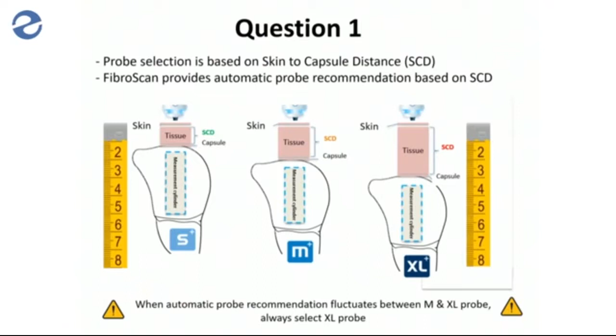We could be tempted, because the XL probe helps applicability of the FibroScan, to scan everybody with XL. We also hear very often that if you compare M and XL probe on the same patient, there are lower values with the XL probe compared to the M probe. What we should stress is that because each probe is dedicated to one type of patient, we shouldn't compare two probes on the same patient, because we are comparing different measurement depths and different ultrasound frequencies. What often happens is, if you scan an overweight patient with the M probe, you get unreliable results because of fat subcutaneous tissue, which makes the results higher with the M compared to the XL. Because of that, we stress the importance of relying on the automatic recommendation tool that you have on the FibroScan.